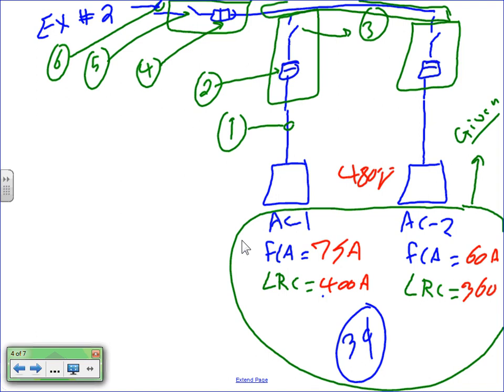Two ACs, the full load amps on the nameplate, Chris. These have compressors in them, so special types of motors, which apply different rules. 75 and 60. The locked rotor current is also given to me. You're going to know why I have the locked rotor current at 3-phase. And we are supposed to size the branch circuit. Number 1 is the branch circuit that goes to AC1. And then, of course, AC2 has its own.